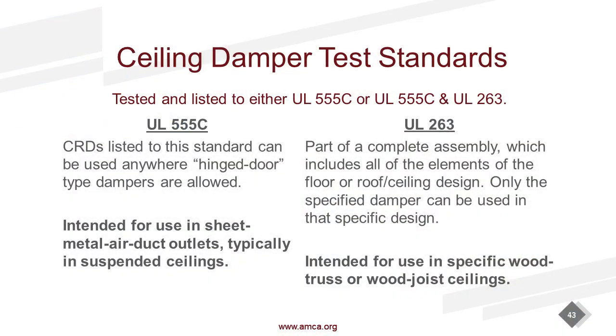There is not a single fire damper approved for installation in a wood-framed ceiling. Period, end of story. Don't ever do it again. I don't care if your engineers put it on your drawing. It's not approved. It should not be done. The simple answer is there's no way to install that damper properly. Nobody's ever tested it. If I can't install it properly, it's not going to protect lives. Now we understand you have a code requirement to meet. So again, call your designers, help work with that. They're a completely different damper.